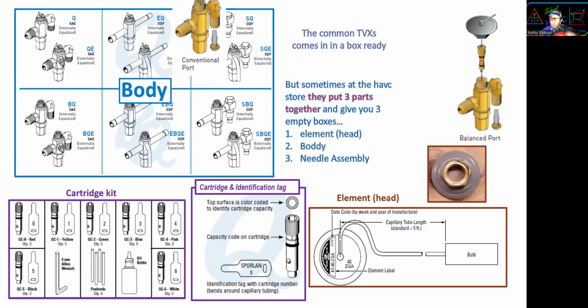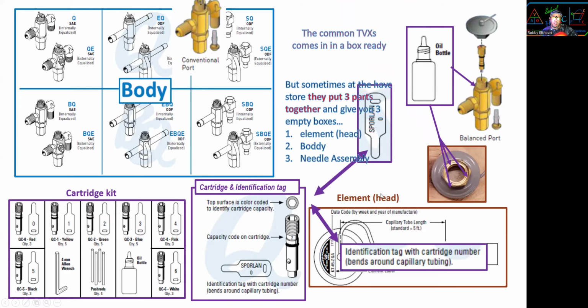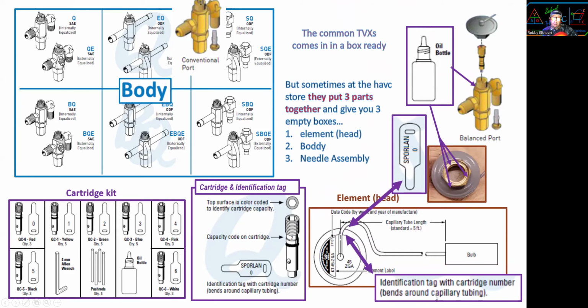They give you 3 parts. They give you a valve and 3 empty boxes. The box is the element: the head is in one box, the body in one box, and the needle assembly in the other box. They put oil on the body and screw in the head. And they put a tag to identify which cartridge is in the valve.